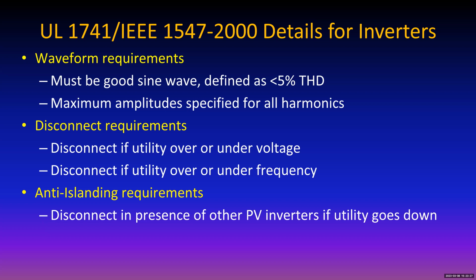Okay, the whole idea is that if you have 4 or 5 or 6 or 10 or 100 of these inverters all close to each other, you don't want one of them to think that the other one is the utility. But if all of them lose their synchronization signal, then they all go off on their own. One of them is probably going to be a little stronger than the other one way or another, and it's going to dominate, and it'll take all the rest of them down with it. So that's pretty important, because that way the world doesn't think that a PV inverter is utility.